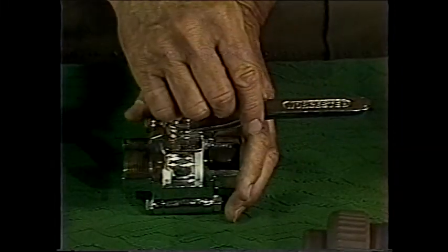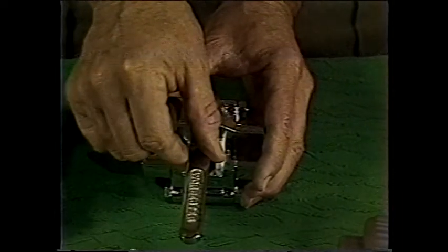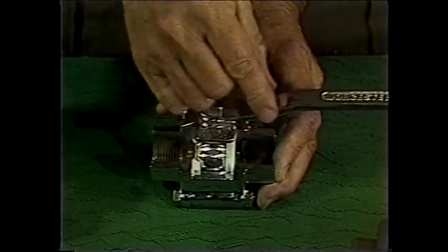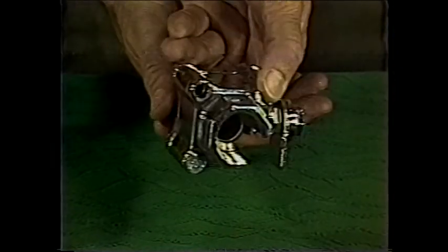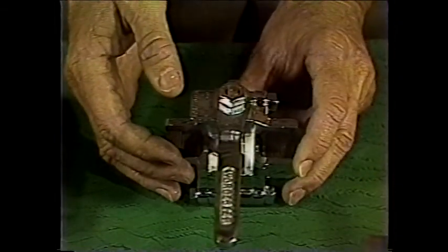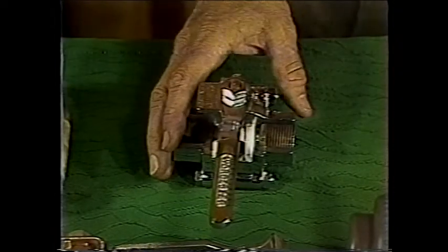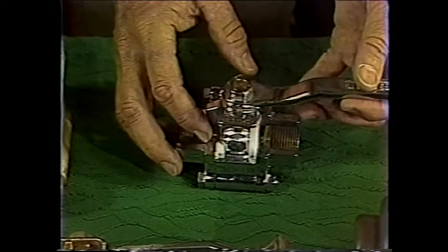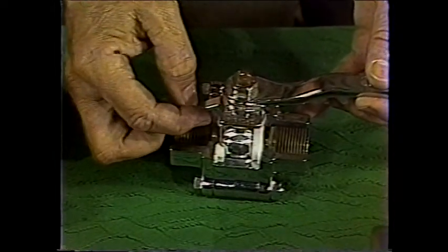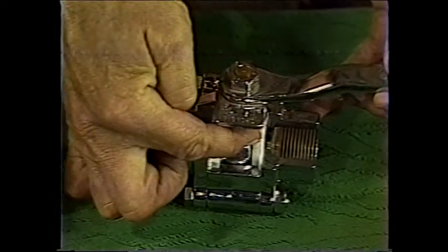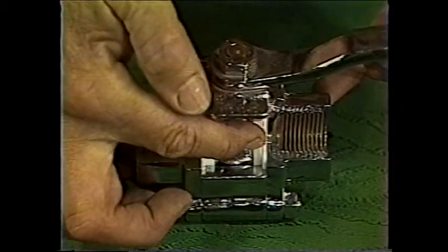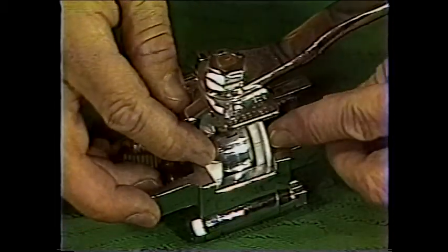The ball valve is very similar in operation to the plug valve, in that a 1/4 turn will move it from full open to full closed. This is open, and this is closed. The position of the handle clearly indicates whether the valve is open or closed. Ball valves are excellent for most off-on service, but are not recommended for throttling applications. With the ball valve, a sphere or ball is used instead of a plug, and the closure is accomplished by a resilient seat here, which is usually some type of rubber or Teflon.